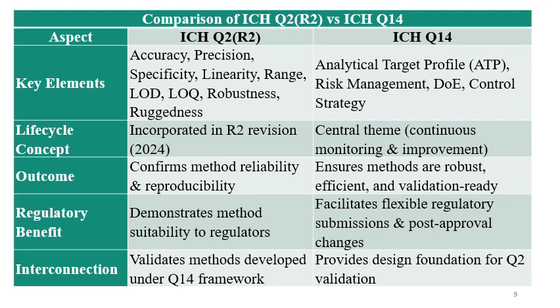Key elements of ICH Q2 are accuracy, precision, specificity, linearity, range, LOD, LOQ, robustness, and ruggedness. Key elements of ICH Q14 are the Analytical Target Profile (ATP), risk management, DOE, and control strategy. Q2 incorporates lifecycle concepts in its R2 revision; Q14 has continuous monitoring and improvement as its central theme. The outcome of Q2 is confirming method reliability and reproducibility; Q14 ensures methods are robust, efficient, and validation-ready. The regulatory benefit of Q2 is demonstrating method reliability to regulators; Q14 facilitates flexible regulatory submissions and post-approval changes.